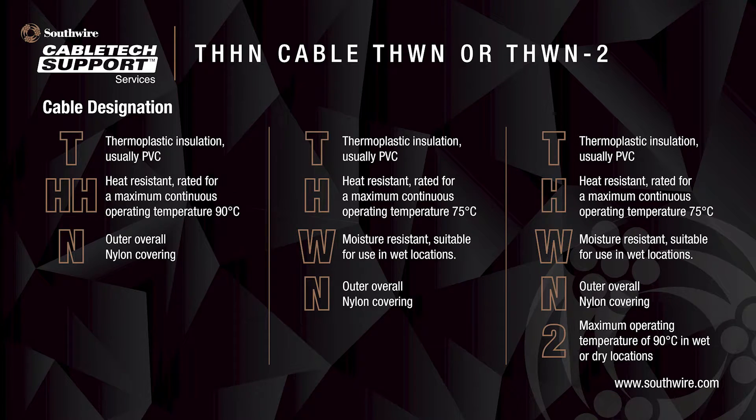Here we see the cable designation for THHN, THWN, and THWN-2. The T stands for thermoplastic insulation, usually PVC. HH is the heat-resistant rating for a maximum continuous operating temperature of 90 degrees Celsius. N is for the overall nylon covering. Where one H is present, it stands for heat-resistant rated for a maximum continuous operating temperature of 75 degrees Celsius. The W gives the moisture-resistant rating suitable for use in wet locations. The DASH-2 rating allows the maximum operating temperature of 90 degrees Celsius in wet or dry locations.